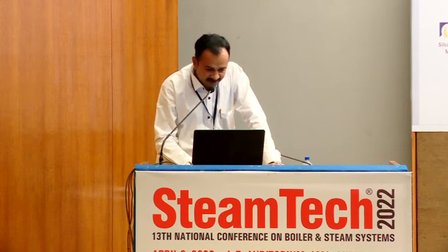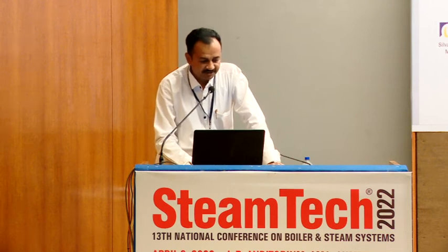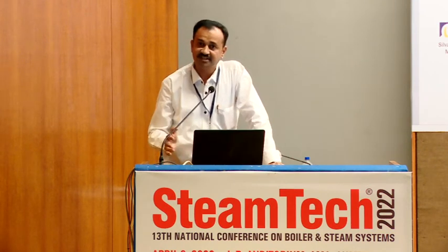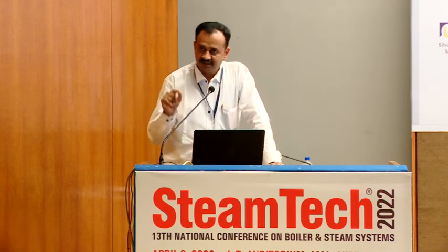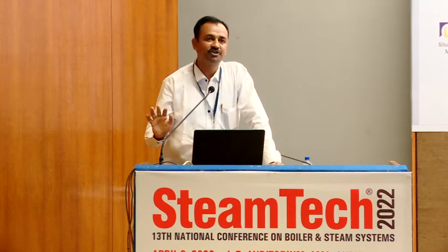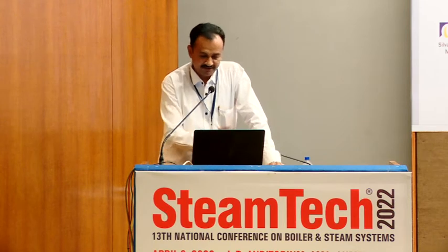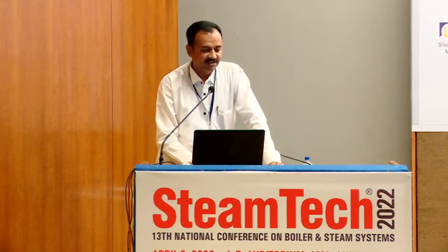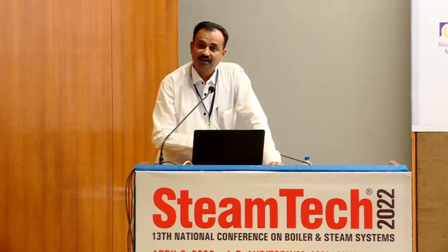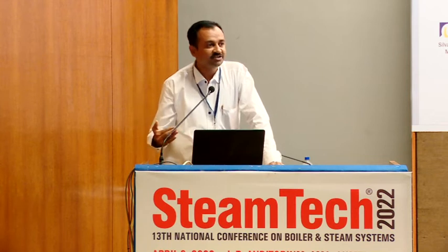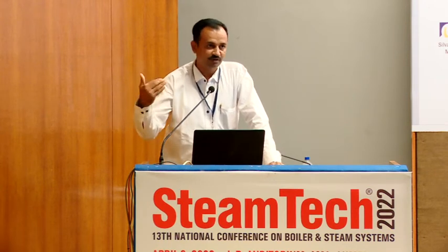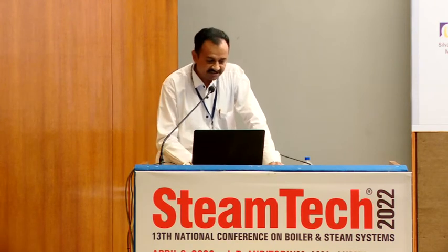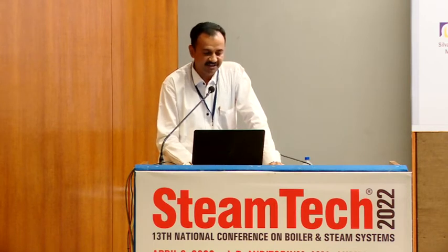Okay. Thank you. So you can see this indirect efficiency band of this and this parameter. This is the optimum we identified, and we try to maintain it. We suggest that you maintain this operating condition regularly, so that you can have the best steam to fuel ratio and best combustion efficiency available. I will not go into this detail, but in a nutshell, it says the 3-level advantage, operator, manager and enterprise level, is a combination of safety and efficiency, where you can see safety parameters like flue gas temperature, drum level, O2 high-low, to avoid vibration and combustion loss or on-off losses. Frequent on-off of the boiler will lead to an unsafe condition. All these things can be eliminated by maintaining the boiler house parameters within the band, so that all three layers can be satisfied with zero downtime.